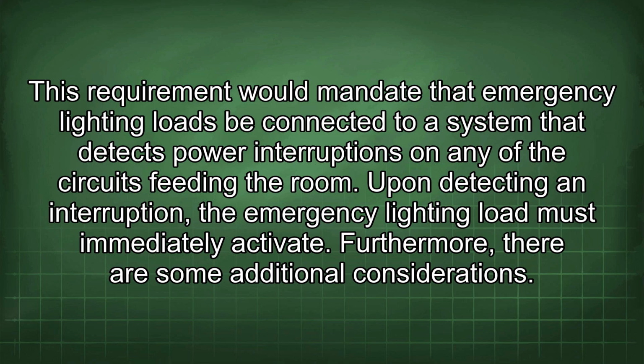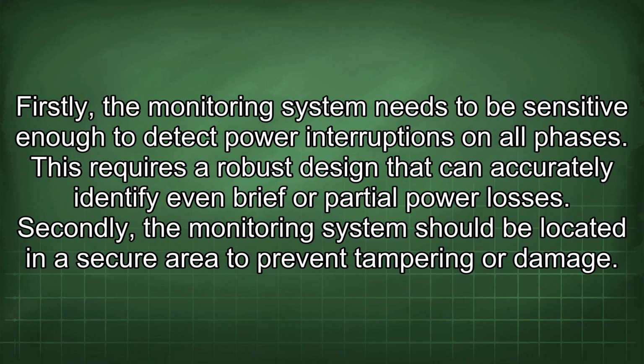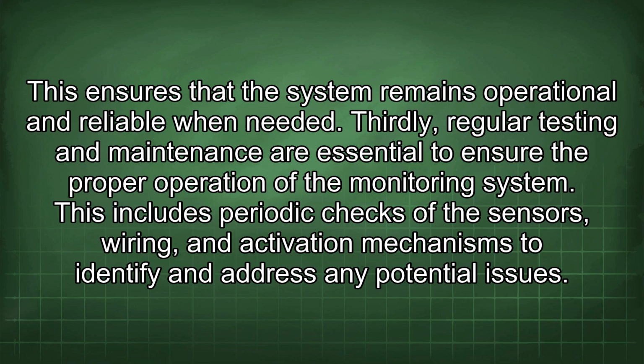Furthermore, there are some additional considerations. Firstly, the monitoring system needs to be sensitive enough to detect power interruptions on all phases. This requires a robust design that can accurately identify even brief or partial power losses. Secondly, the monitoring system should be located in a secure area to prevent tampering or damage. This ensures that the system remains operational and reliable when needed. Thirdly, regular testing and maintenance are essential to ensure the proper operation of the monitoring system. This includes periodic checks of the sensors, wiring, and activation mechanisms to identify and address any potential issues.